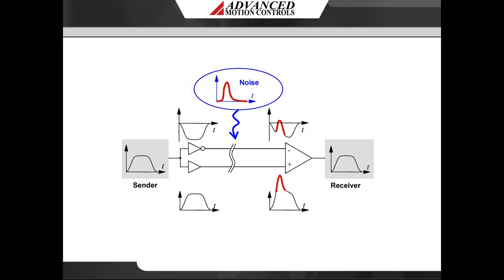If the command input is a plus or minus 10-volt analog signal, it is recommended to use differential inputs at the drive to eliminate common mode noise. In doing so, EMI common to both signals will be ignored. A differential signal is more immune to electromagnetic interference than a single-ended input because the common mode noise signal is cancelled at the receiver when the differential signal is taken. Network commands such as EtherCAT or CANopen are not susceptible to this type of noise.